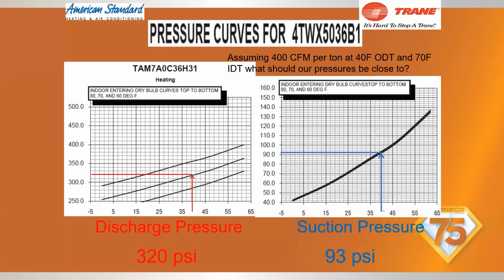Going back to this, with the pressure curves, we want to get it close. And it is not published information, but we look for it in heating. So in cooling, we want about a 10-degree subcool. So if you're measuring that liquid line temperature at the condenser on the outdoor unit, well, it's not a condenser in heating mode, but if you're measuring that line, in heating we want about a 25 to 30 degree subcool, where you have found that that's a good effective subcool.